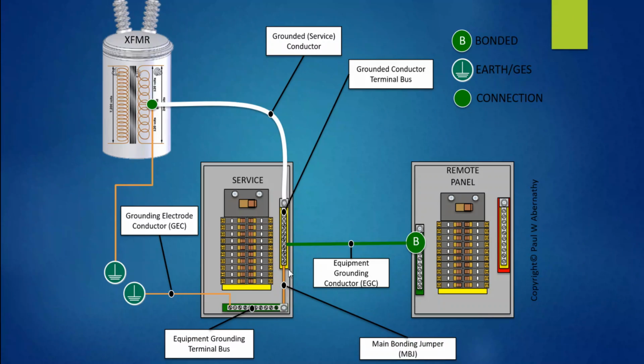So here you go. Here's the two buses tied together. This is the option here. Now, if this part down here wasn't there and everything was being done by one bus, then this grounding electrode conductor would make a connection up here to this bus, because the code requires it to connect directly to the grounded conductor, or the bus that connects to the grounded service conductor. But there is an allowance in the code to do it this way if you use this wire type.